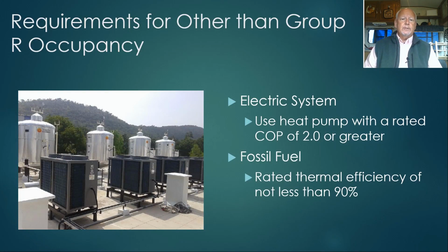So what are the requirements? If it's an other than Group R occupancy and they meet the requirements for a high input water heating system, if it's an electric fuel system, then you shall use a heat pump with a rated COP of 2.0 or greater. If it's a fossil fuel system, you have to use equipment with a rated thermal efficiency not less than 90%. So again, electric system, heat pump with a coefficient of performance 2.0 or greater. If it's a fossil fuel system, high efficiency, not less than 90%.